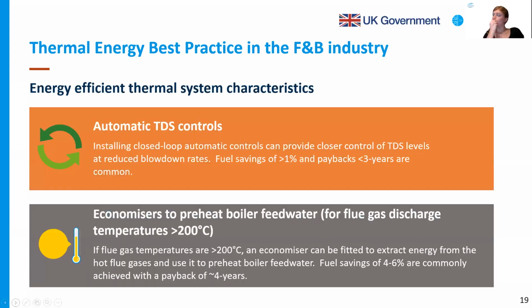We already talked about automatic TDS control, so I won't spend more time on this. Another option below is using economizers to preheat boiler feed water. That's also something that we already saw, with fuel savings in the range of 4 to 6%.